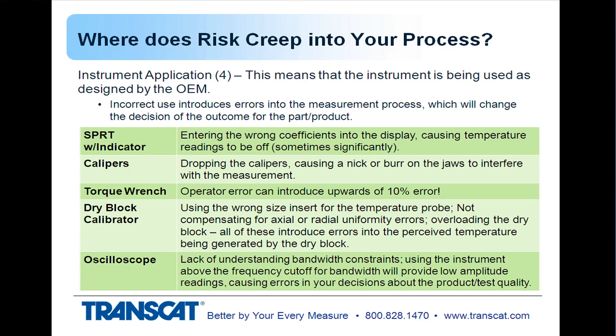Dry block calibrator is another good example. There are so many different types of influences an operator can have in not transmitting the temperature properly. From the wrong size insert for the temperature probe being used, to not compensating for axial uniformity, which is from the top to the bottom, versus radial uniformity, which is from well to well. Overloading it, putting too much into it, can cause the temperature transfer to be incorrect. So you may think you're generating a certain temperature from a drive block calibrator, and you're not actually getting that. And that introduces error, which changes the result of your testing of your product.